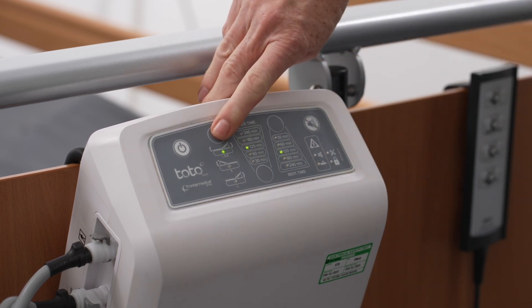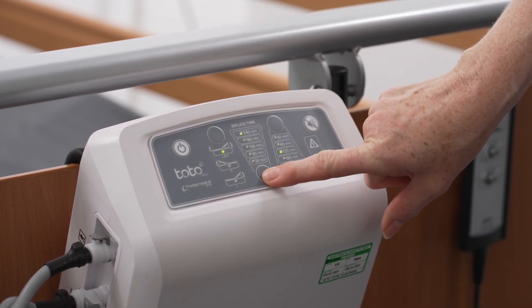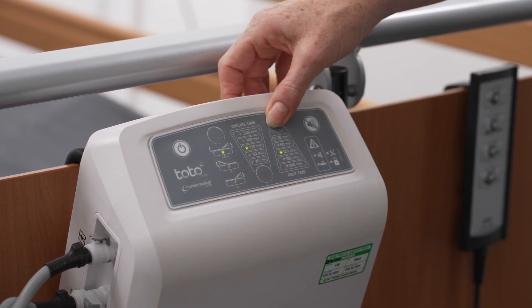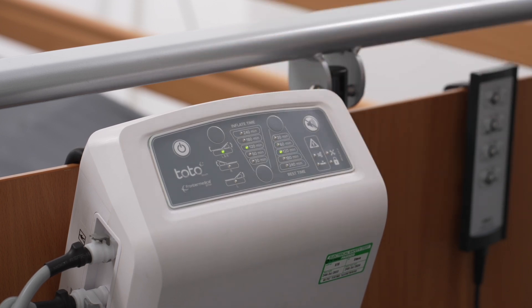To change the default settings, press the button to scroll through the LED lit options until you have arrived at your preferred choice. A healthcare professional should determine inflation and rest durations. Air cell inflation begins and each side remains inflated for the duration that is selected. If the control unit is turned off, it reverts to the default settings when switched back on.